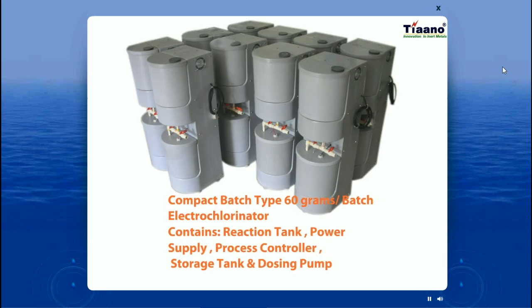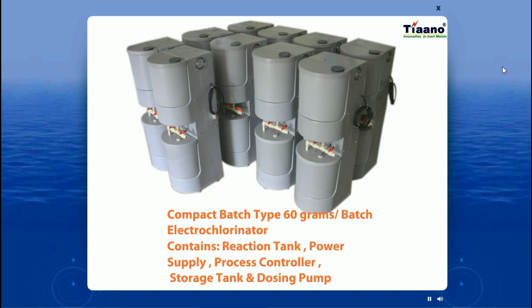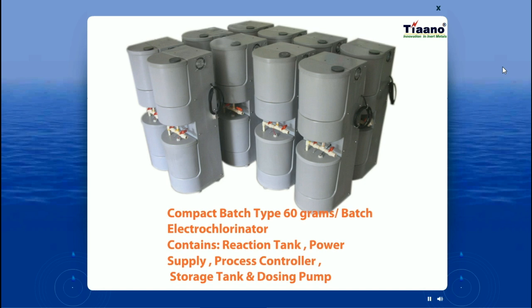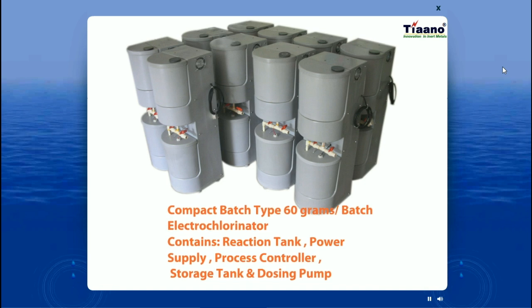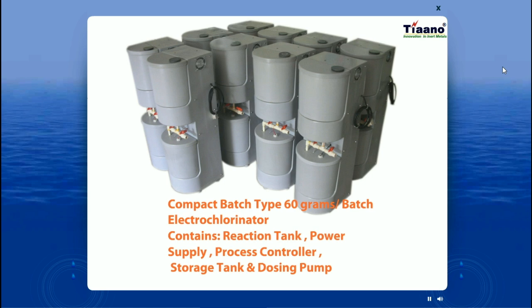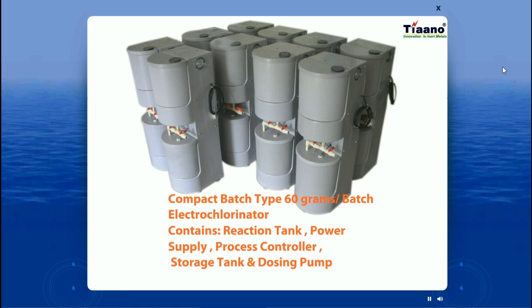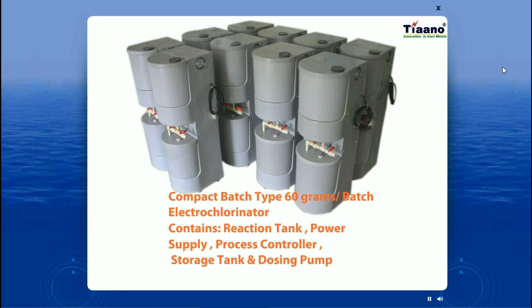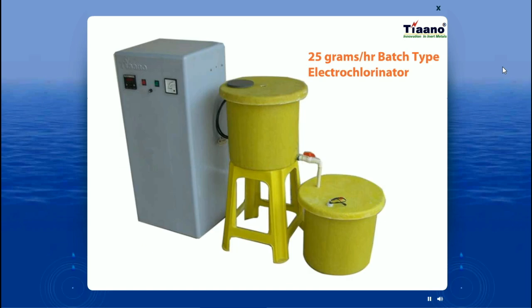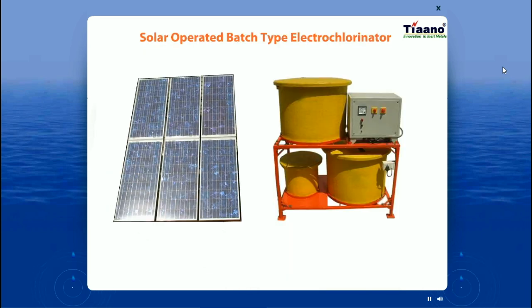Our compact chlorinator is one of the smallest batch-type units, producing 60 grams of chlorine capable of disinfecting 30,000 to 50,000 liters of water. Salt and water are put in the top chamber, power is switched on, and in eight hours the sodium hypochlorite produced is transferred to the bottom tank, from where it is dosed by a dosing pump. Batch process electrochlorinators can produce up to 400 grams per hour of chlorine. In remote areas without electricity, the electrochlorinator can be operated using solar power.